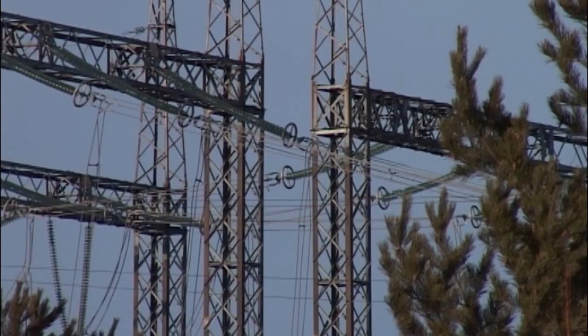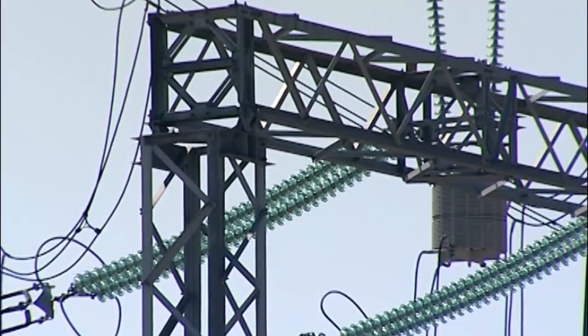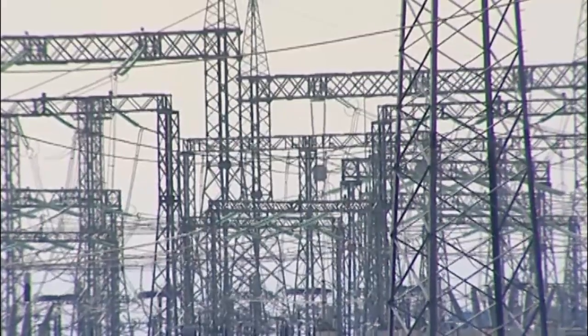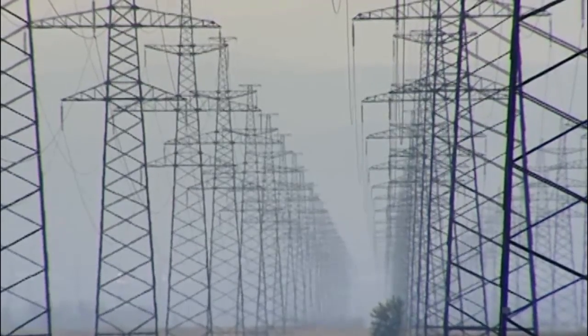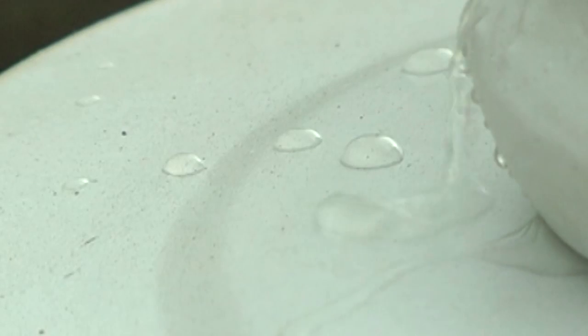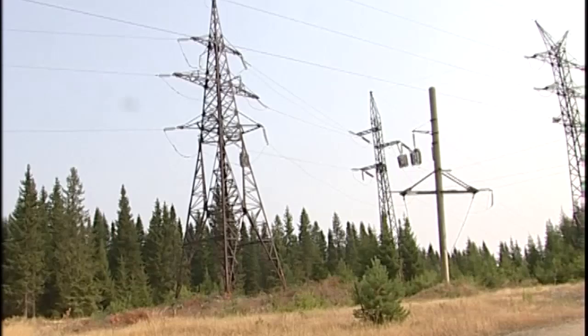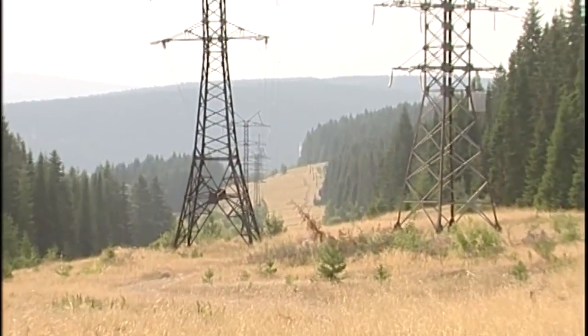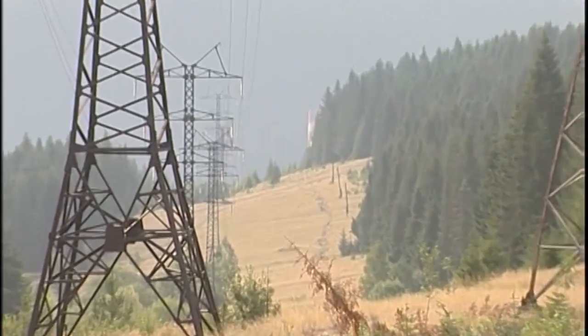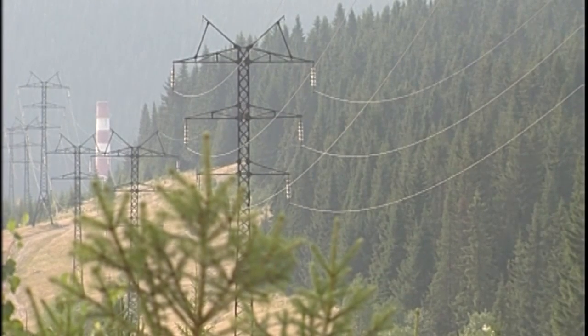One type of contamination of insulators in the atmosphere is emissions from industrial enterprises, which produce an acid reaction on the alkali glass surface, exposing the glass to erosion. Over time, NSDD and ESDD deposits accumulate on the surface. Some are cleaned by rain and wind, while others are not. Selecting the design of the glass part and material before installation is essential to protect against deposits.